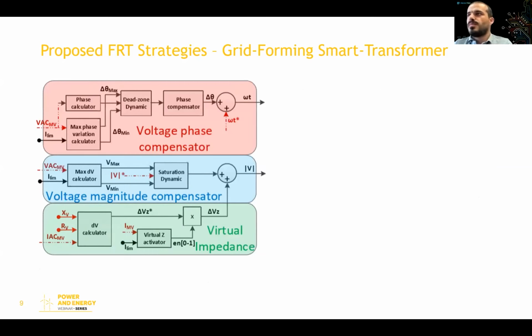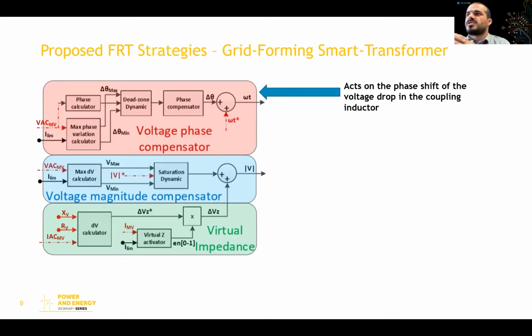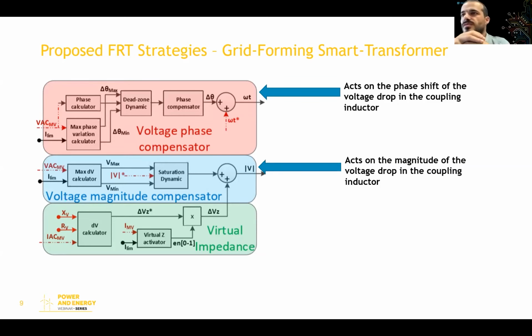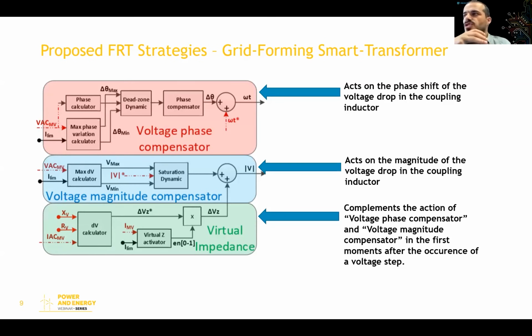This method also relies on three components, but their functions are quite different. We have a voltage phase compensator, which acts on the phase shift of the voltage drop in the coupling inductor, and is responsible for regulating the active component of the current. Then we have the voltage magnitude compensator, which acts on the magnitude of the voltage drop in the coupling filter, and is responsible for regulating the reactive component of the current. And then we have a virtual impedance, which complements the action of the previous two. It is very useful in the first moments after the occurrence of the voltage step, falling or rising, where the demanding controllability is more critical.